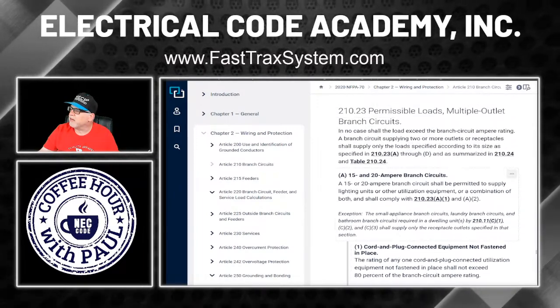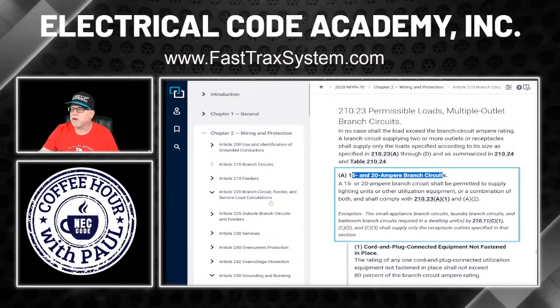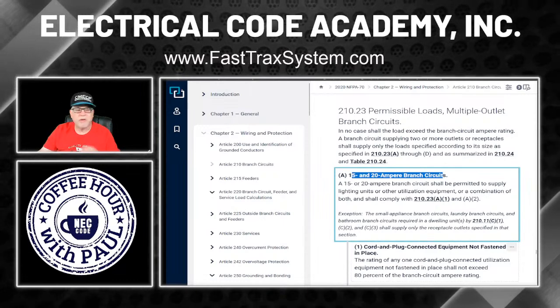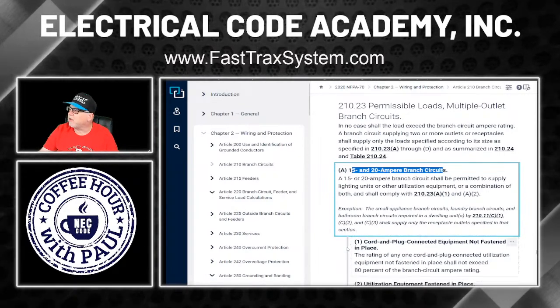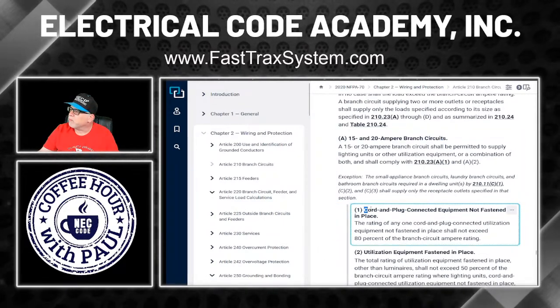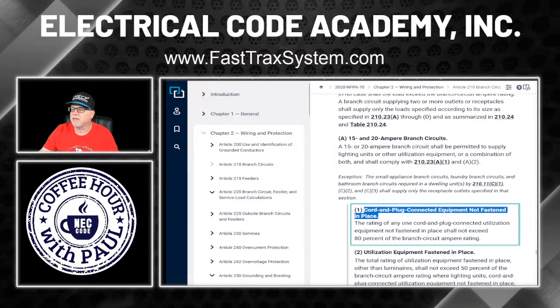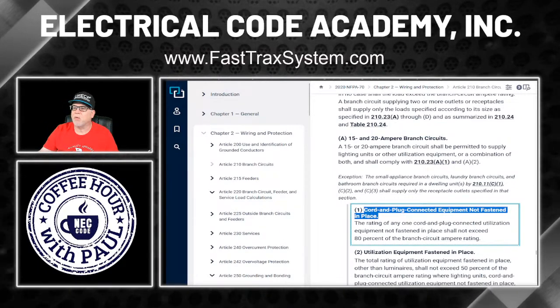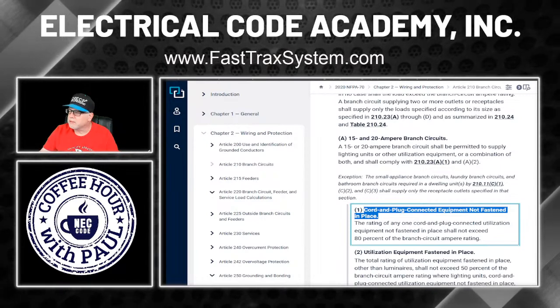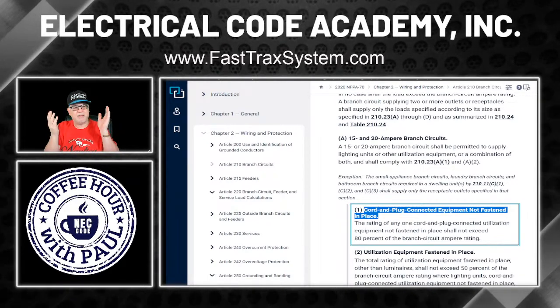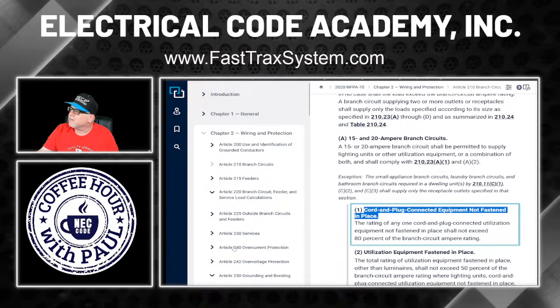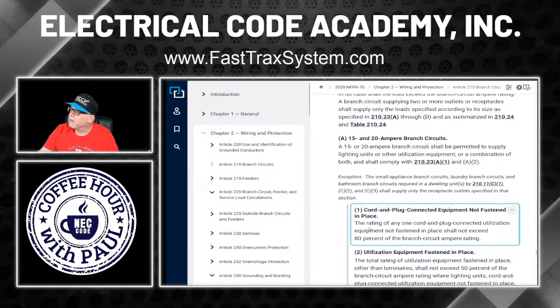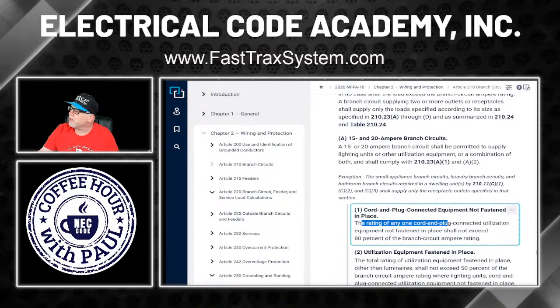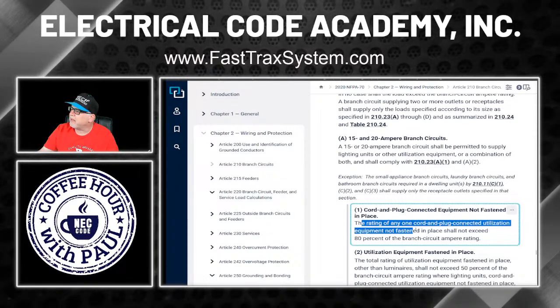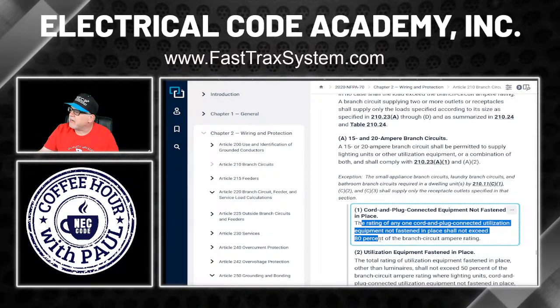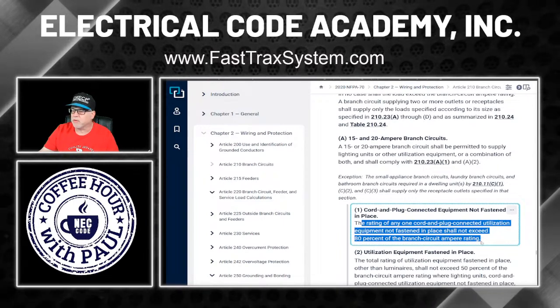Okay, what do you see here? 15 and 20 amp circuit. This was a 20 amp circuit. Remember we said the reason for writing these things down? Right here: cord and plug connected equipment not fastened in place. All right, so this says any one cord and plug portable. Okay, so it's obviously not fastened in place. It says the rating of any one cord and plug connected utilization equipment not fastened in place shall not exceed 80% of the branch circuit's rated amperes.